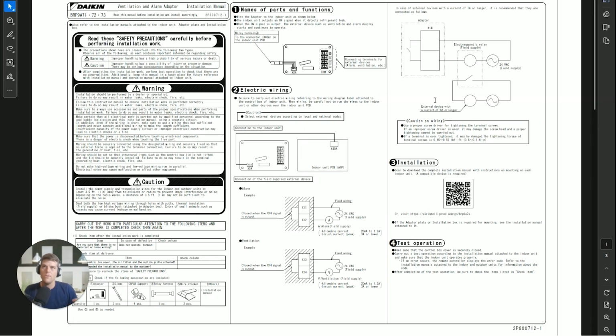Remember, when we talk about refrigerant mitigation within a space, it's usually just killing the cooling cycle, running the fan. And with that, there's always a few other additional caveats when it comes to VRV, and maybe the unit that's in that space exceeds the limitation amount that you're supposed to have. And so you have to have accessory contacts to run fans, to purge, to ventilate, to alarm. It's nothing crazy. Just know that some of the indoor units do have that ability already built into the board, and some of them do not. They're not crazy complicated, but these are the big changes that we're going to be seeing.